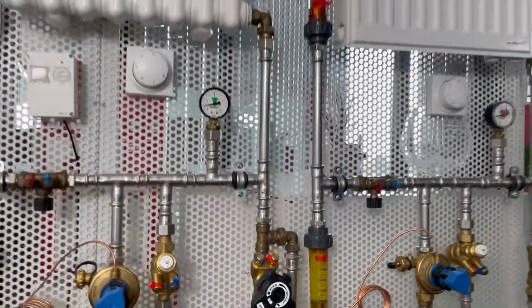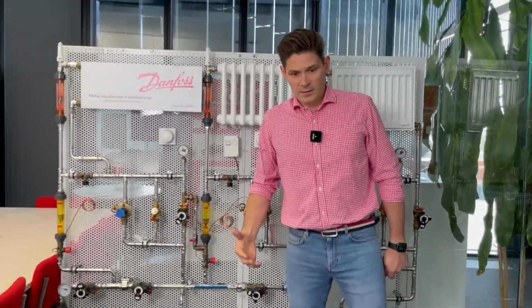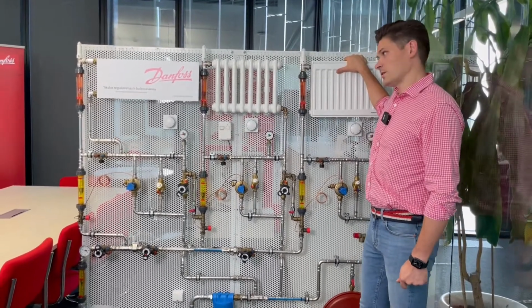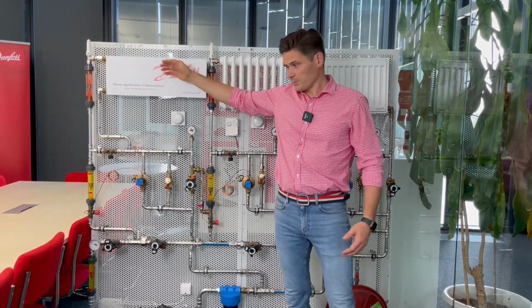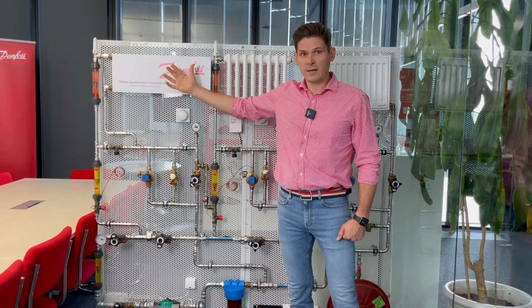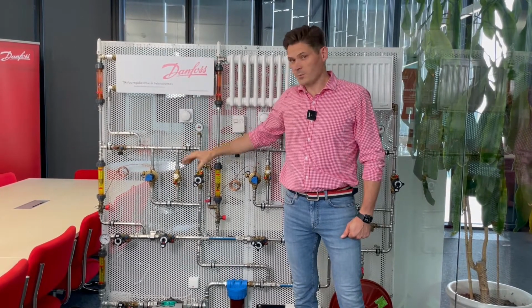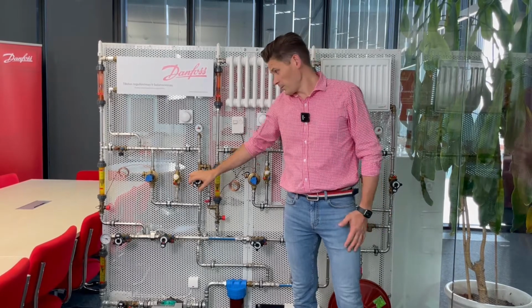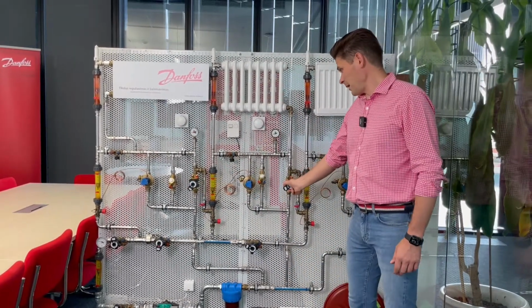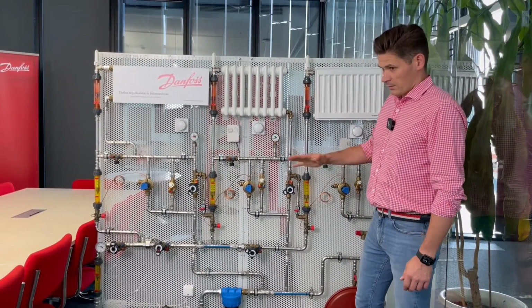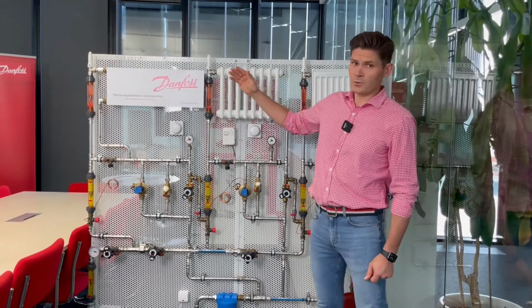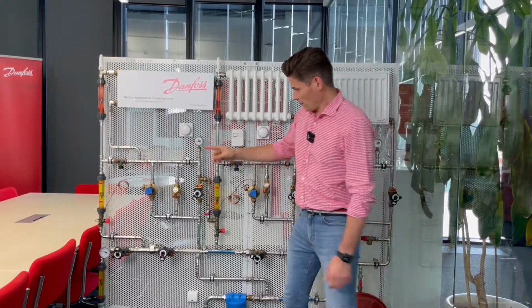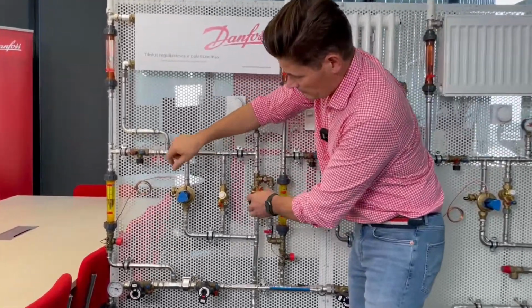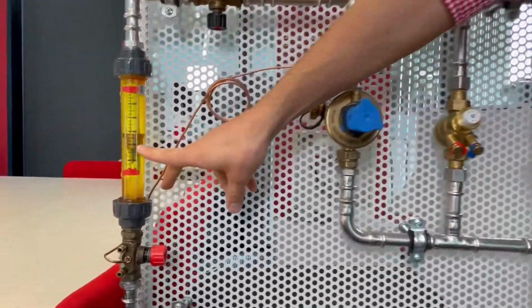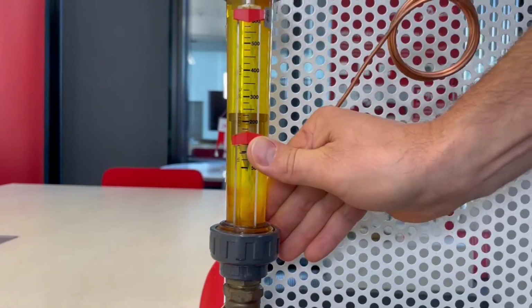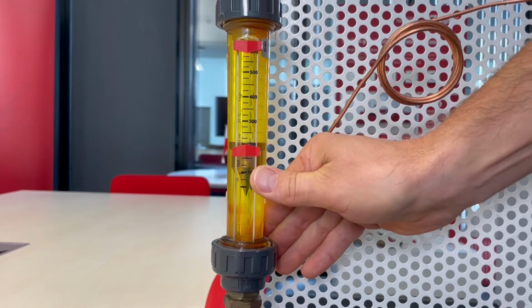Okay? So there is a problem in the house that the last riser is not heating enough and the first riser is heating too much. So there might be an idea to balance the system, and somebody would advise to put manual balancing valves on each riser. Let's try to put manual balancing valves here and balance the system with manual balancing valves. Let's say we need 200 liters for each riser, first, second and third. So now I simply regulate the manual balancing valve and I'm trying to achieve 200 liters. Okay, I want to balance it at 200 liters.